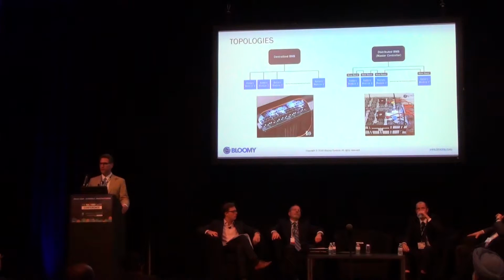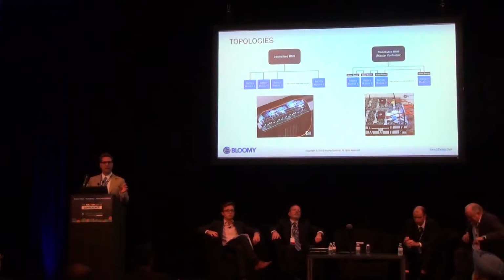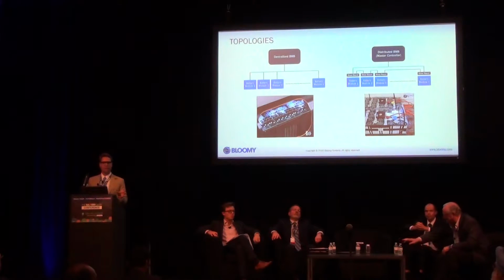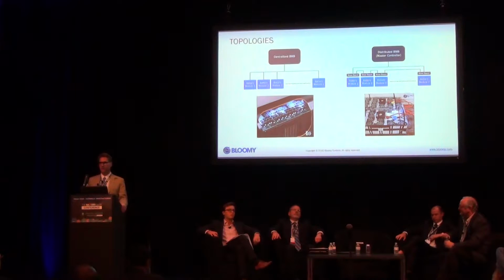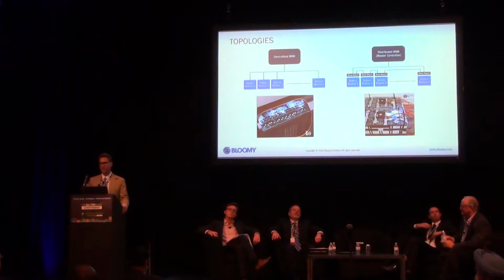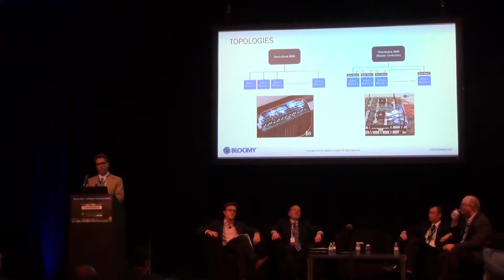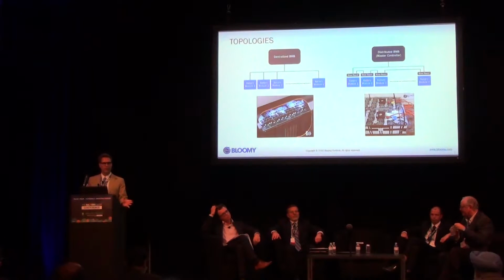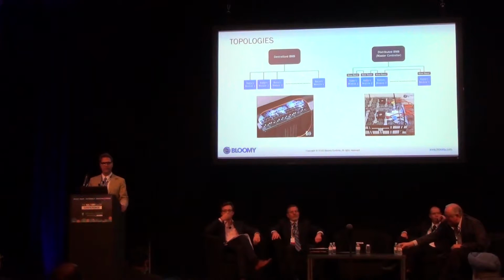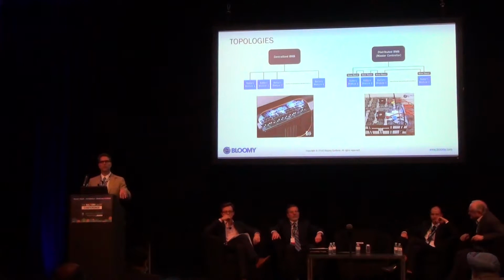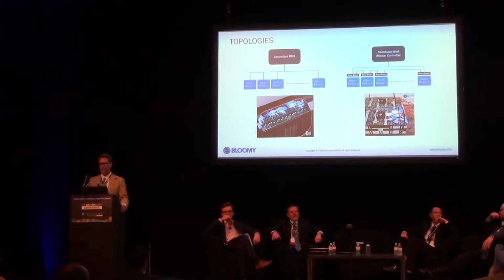And then there's a distributed BMS architecture where you've got a slave board that is responsible for monitoring the individual cells or groups of cells as modules. It monitors the current, voltage and temperature of those small groups of cells, and then communicates back to the master controller what all of those cell values are. The balancing is usually performed at the module level by these slave boards.